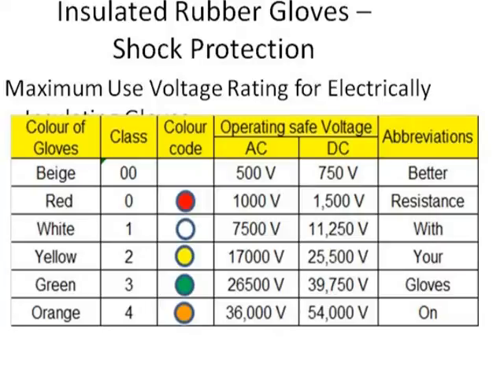There are different color codes for each class. You can remember them with the abbreviation: 'Better Resistance With Your Gloves On.' B stands for beige — class double zero. R stands for red — class zero. W stands for white — class one. Y stands for yellow — class two. G stands for green — class three. O stands for orange — class four. For operating safe voltages, class double zero handles AC 500V and DC 750V, and so on for higher classes.